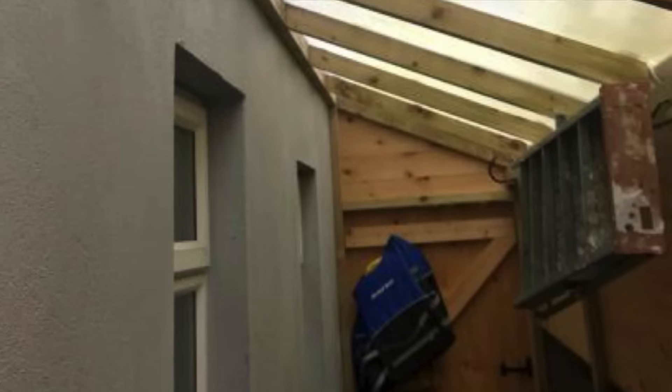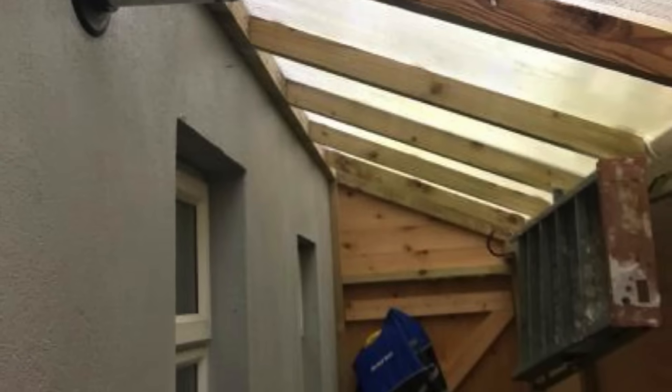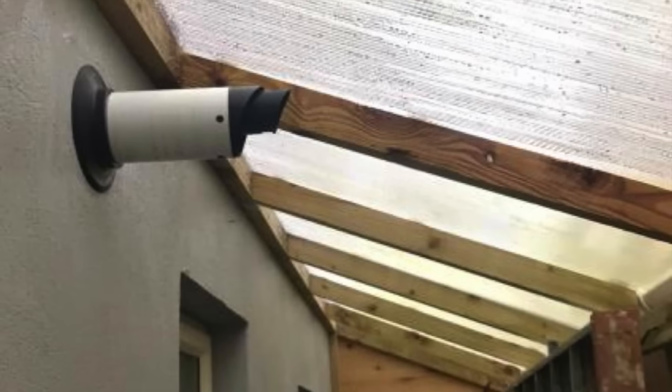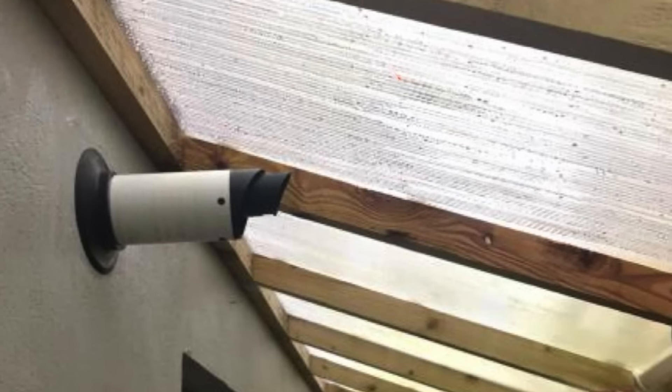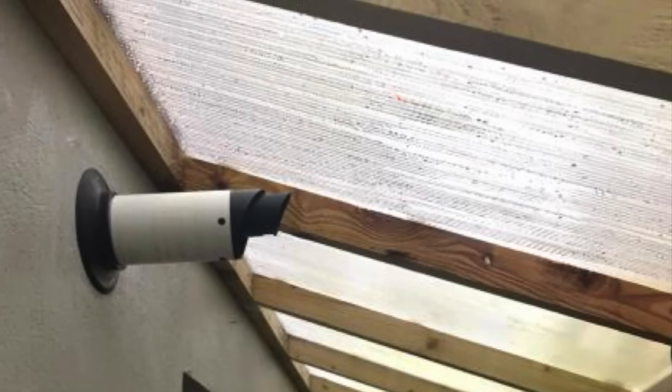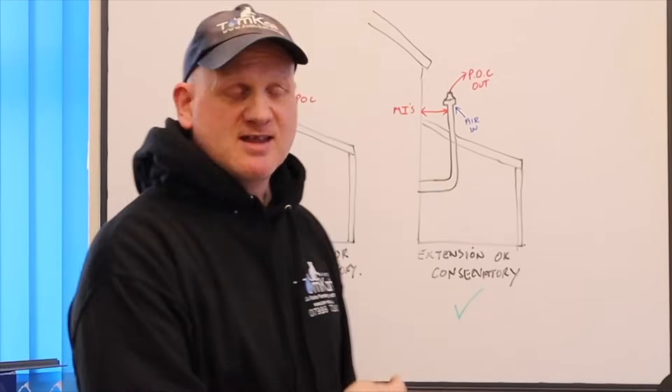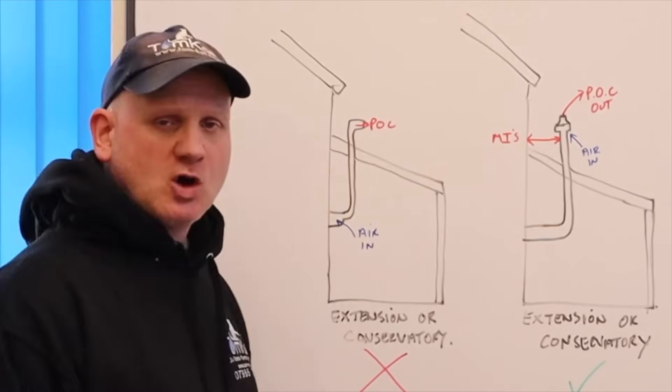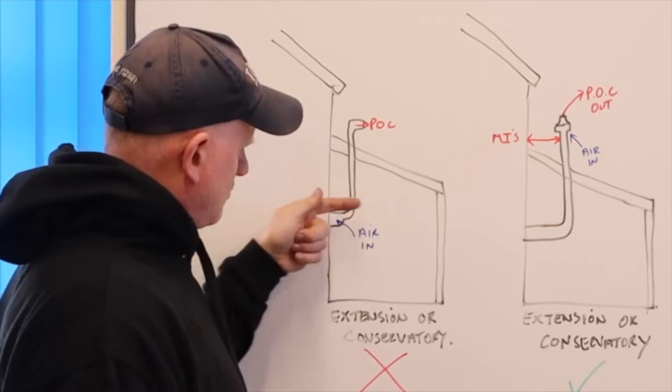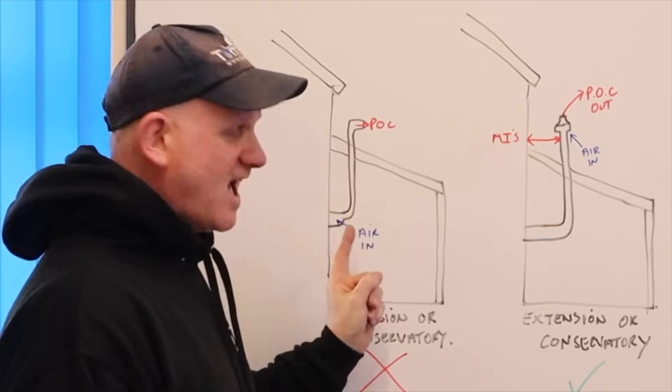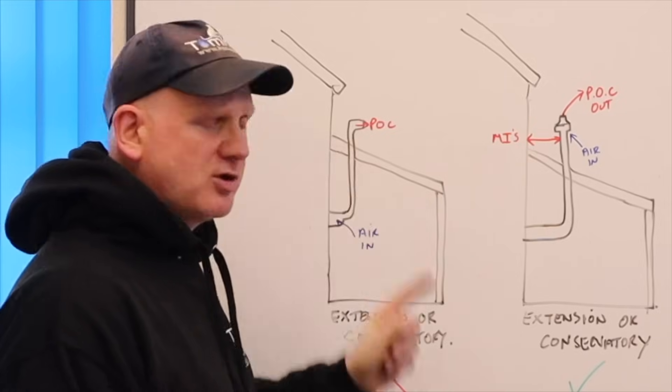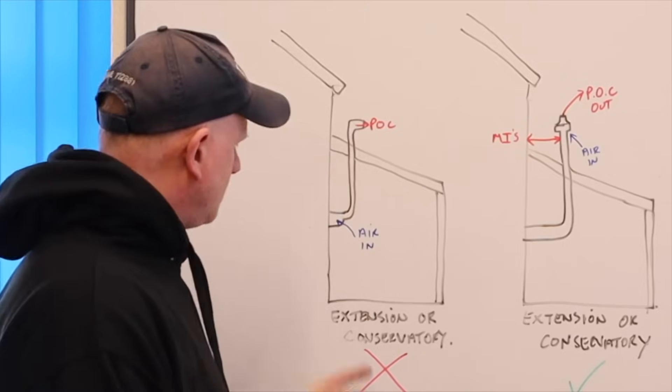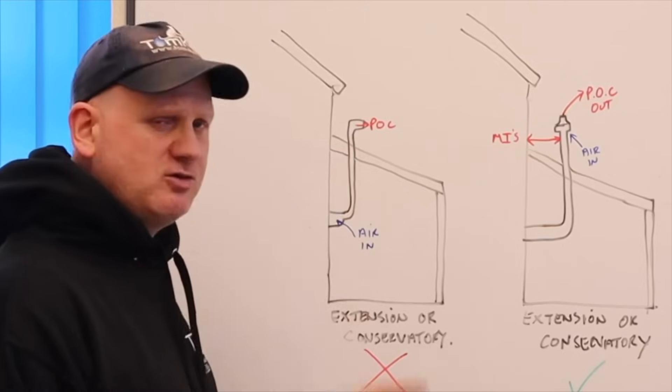Now, in this situation, we've got a little lean-to what's been built onto the side of a house where the flue terminates. Now, can we use a plume management kit to overcome this problem? Now, one of the things you can't do with a plume kit is this. So, this is an extension or a conservatory. And this is the old position of the flue. So, the products of combustion came out here. You cannot use a plume kit to take the products of combustion out through the roof and leave the air intake coming in your kitchen extension or conservatory. You cannot do that.